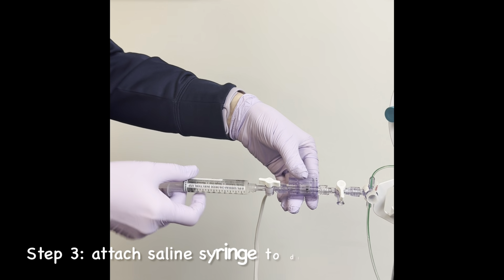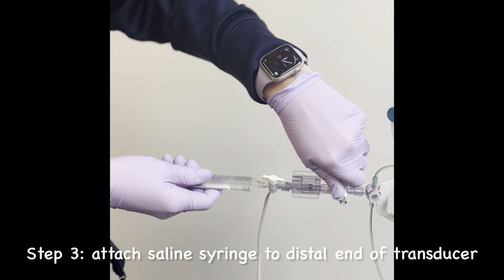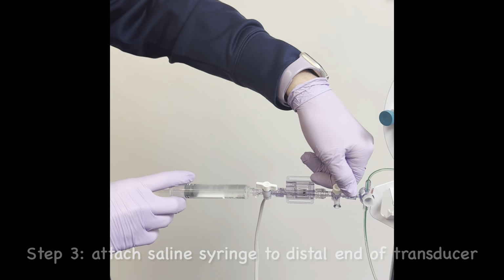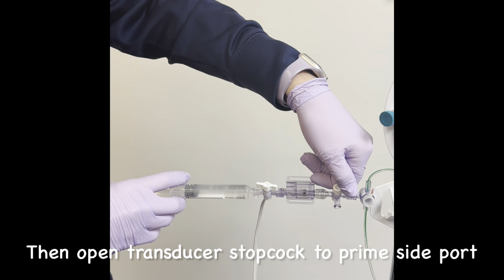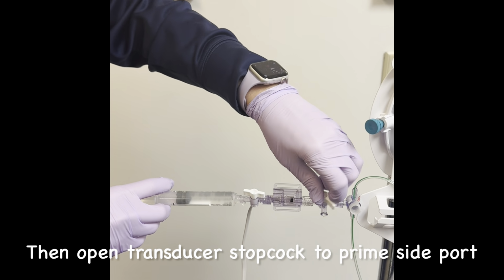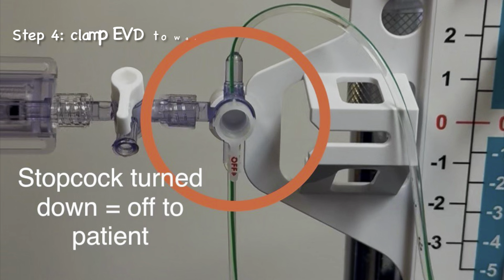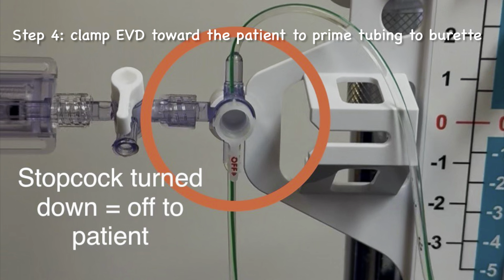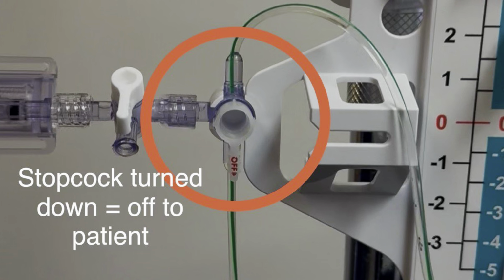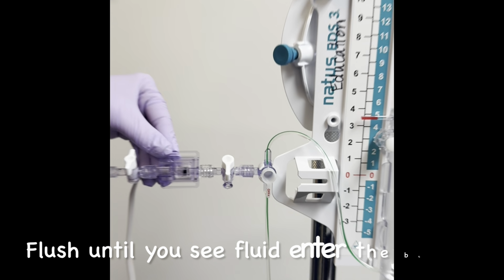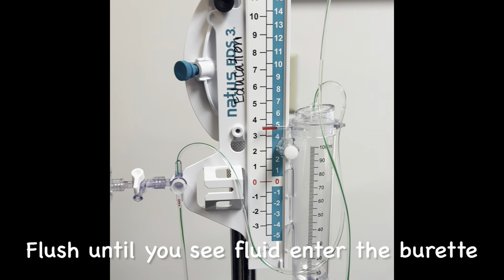Step 3. Attach the saline syringe to the distal end of the transducer. Open the transducer stopcock and flush to prime the side port. Close the transducer stopcock. Step 4. Clamp the EVD to the patient by turning the EVD drainage system stopcock to the down position. Flush the saline until you see fluid enter the burette and all bubbles have been removed from the tubing.